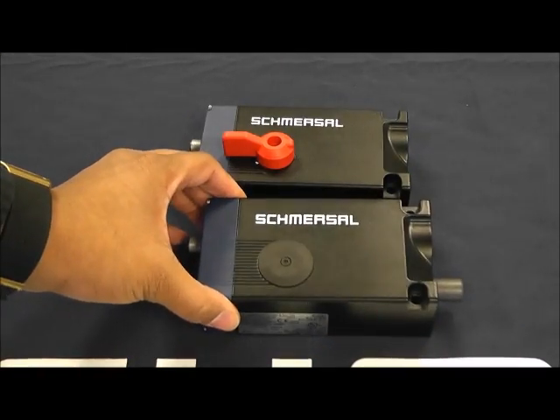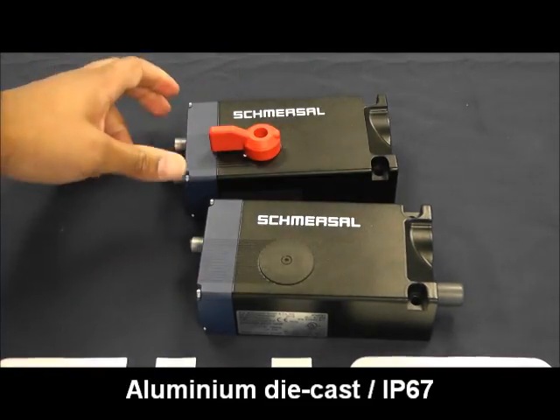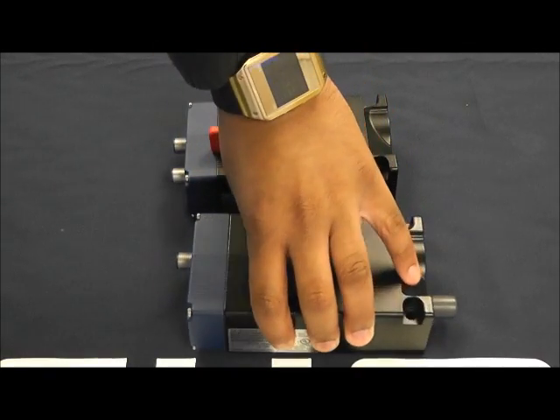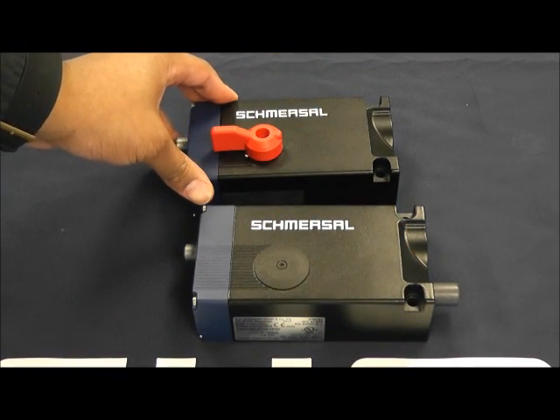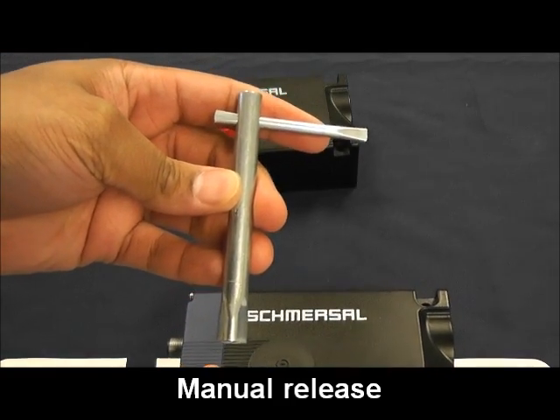Looking at the AZM 400, you'll notice that it is a robust switch with its aluminum die cast housing. With the Schmersal RFID technology, you have three LEDs for quick and easy switch status and error codes. In case of having to override the bolt lock function for emergencies or special operating modes, options allow for an emergency T-handle located on the inside of the hazardous area, or by default under this cap is a triangular knob which requires the use of the accessory AZM key.